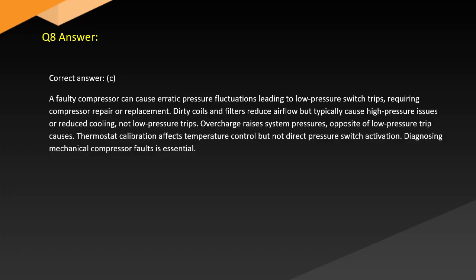Answer. Correct answer: C. A faulty compressor can cause erratic pressure fluctuations leading to low pressure switch trips, requiring compressor repair or replacement. Dirty coils and filters reduce airflow but typically cause high pressure issues or reduced cooling, not low pressure trips. Overcharge raises system pressures, the opposite of low pressure trip causes. Thermostat calibration affects temperature control but not direct pressure switch activation. Diagnosing mechanical compressor faults is essential.